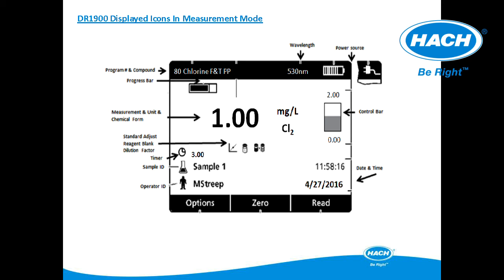Besides the measurement information previously discussed, there are additional software features that make the DR-1900 versatile and suitable for multiple applications. The DR-1900 has a timer function that is saved for those programs that require a specific time for reaction. Using the advanced options menu, a standard adjust, reagent blank, chemical form, or dilution factor can be entered. The icons are displayed on the measurement screen during the measurement and in the data file for easy recognition. The progress bar provides easy recognition of when the method and measurement is complete and results can be recorded.